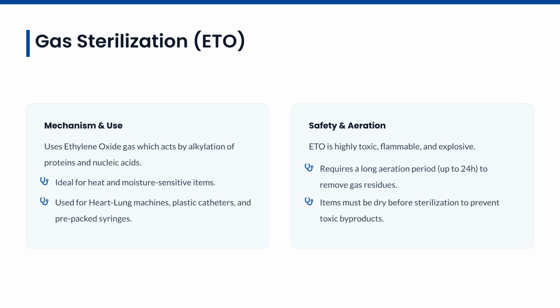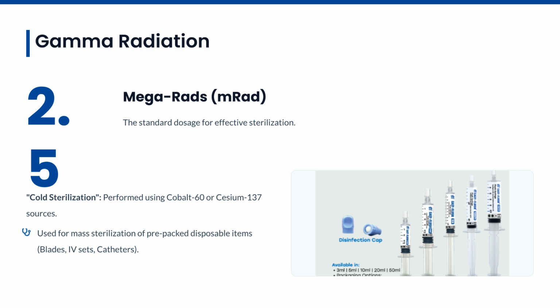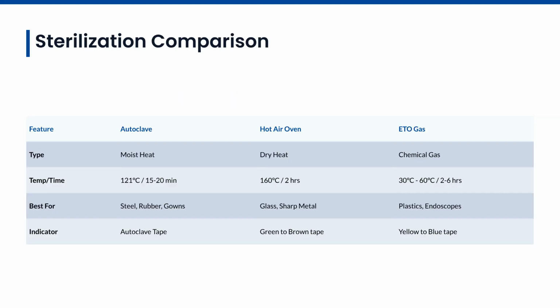Gas sterilization uses ethylene oxide, or ETO, which acts by alkylation of proteins. It is ideal for heat and moisture-sensitive items like plastic catheters. ETO is toxic and flammable, requiring a long aeration period of up to 24 hours to remove residues. Gamma radiation is known as cold sterilization. It is performed using Cobalt-60 and requires a standard dosage of 2.5 megarads. This method is used for the mass sterilization of pre-packed, disposable items like blades and IV sets. This final slide summarizes the main sterilization methods, comparing their mechanisms, uses, and limitations.